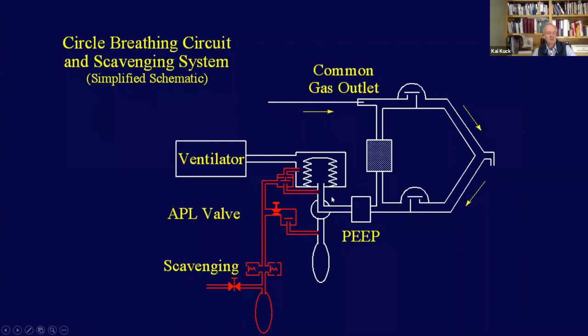And when the bellows hit the top here, any excess gas gets scavenged out. And there's what they call an APL valve, and that basically determines the pressure at which this valve opens. So this would be the anesthesia machine, and I know that you've heard about it from Patrick, and I just want to maybe have a little bit of discussion here.